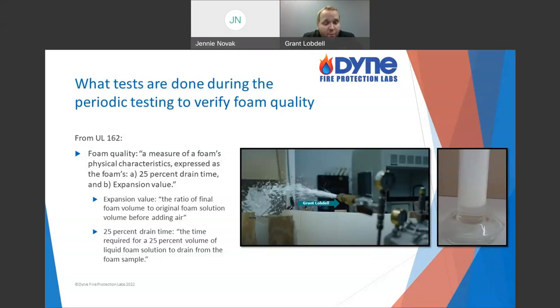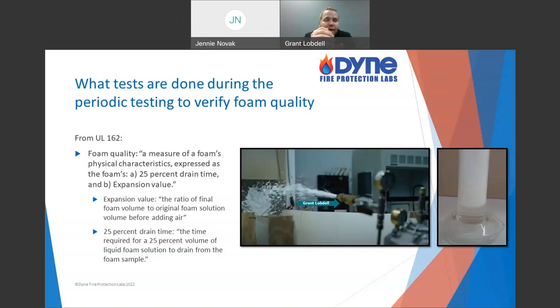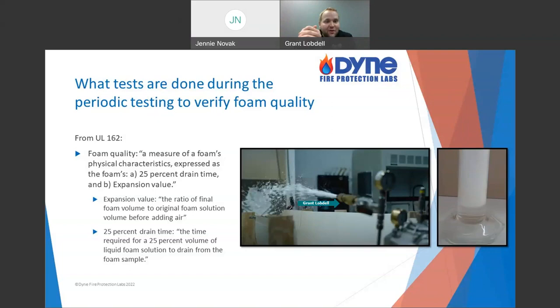Expansion ratio is very important. Then there's 25% drain time, or drain time in general. A foam blanket sitting on top of the fuel smothers it, cuts off oxygen, and may cool it. But it does me no good if I'm fighting a fire to my left, get that foam blanket covering it, start putting it out, and then by the time I turn to my right, the stuff on the left has dissolved and disappeared. So we need it to last a certain amount of time — a certain drainage rate.